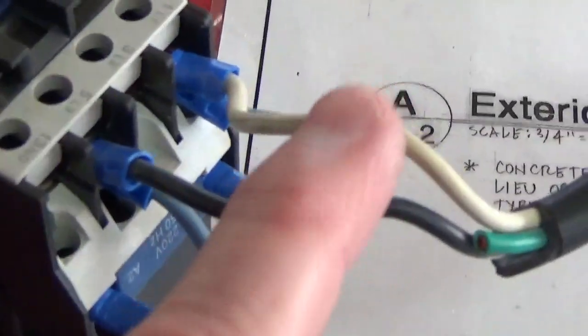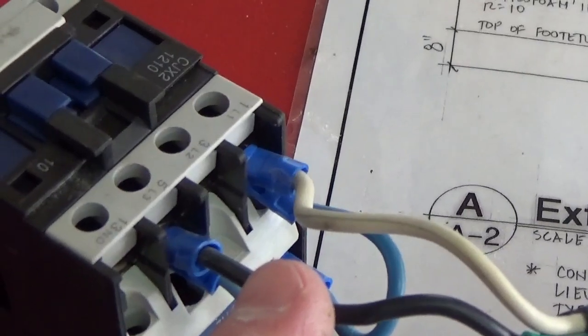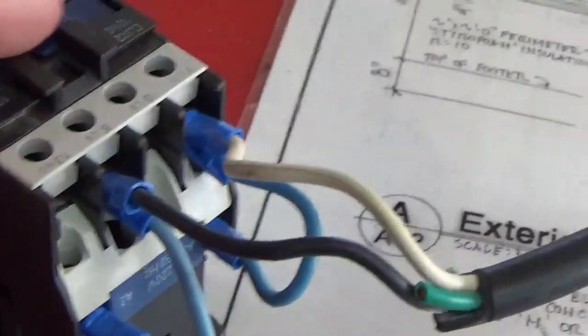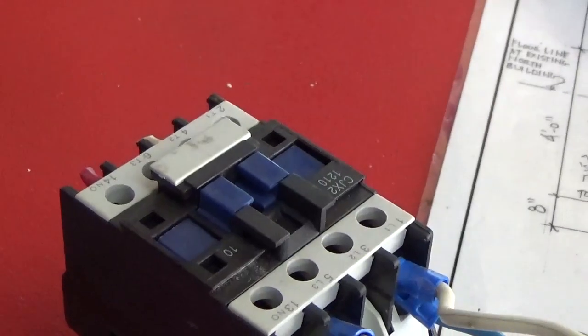The contactor here, the white and black, is where your 220 volt comes into the unit to power it, and it connects up to these two terminals, an L3 and an L1. So when you have power, push in the button, it connects these two wires here, pulls the contactor in, which pushes this down, connects these two wires on this side to the two wires on that side, powers the lift, and up you go.